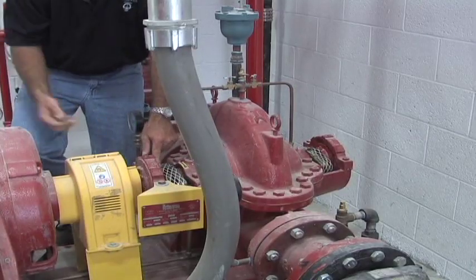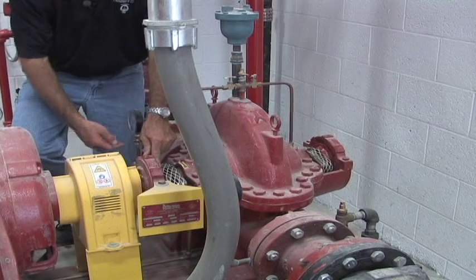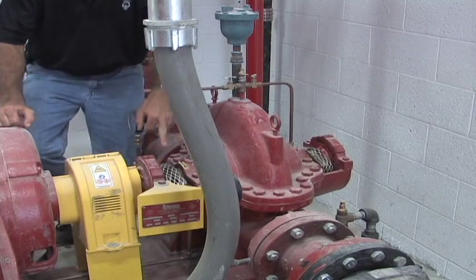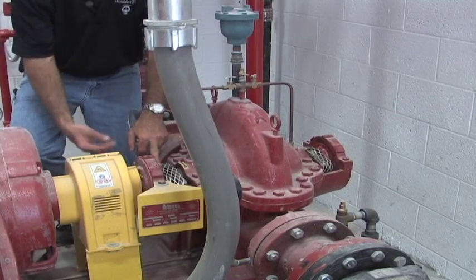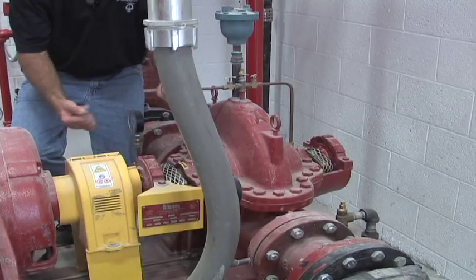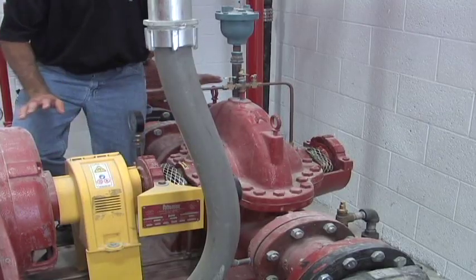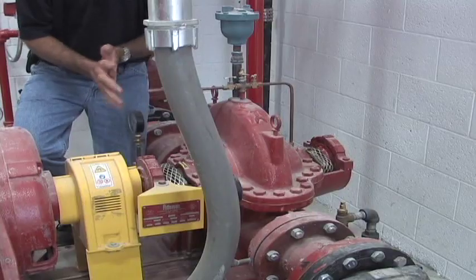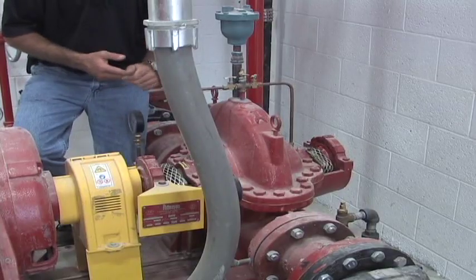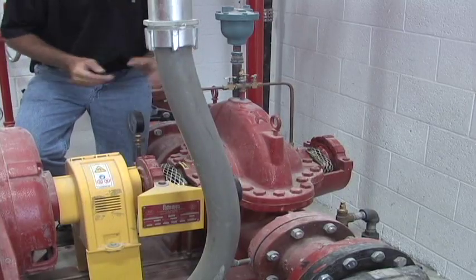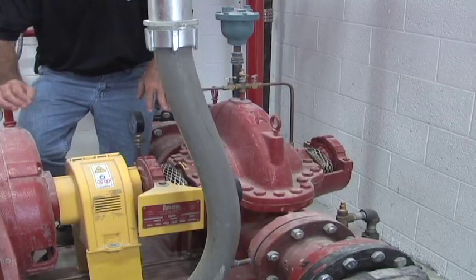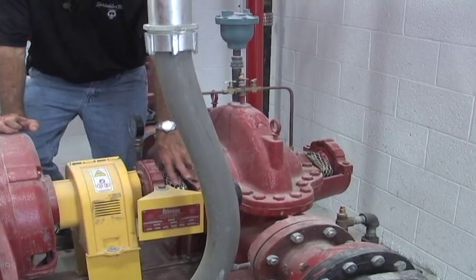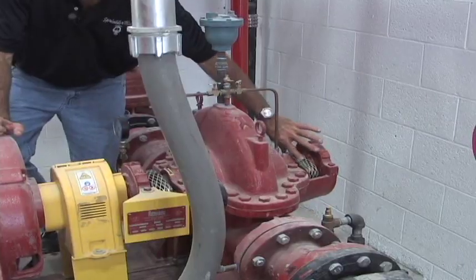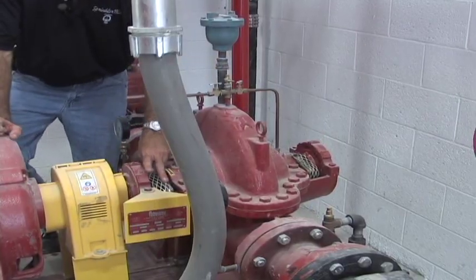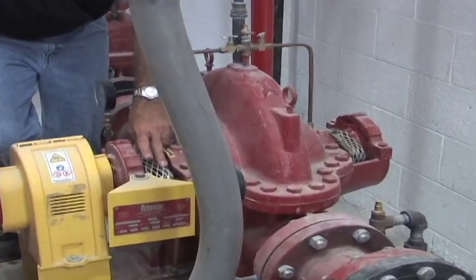You're going to grease here, you're going to pull the Allen wrench screw out of the bottom, you're going to pump new grease from the top until the old stuff comes out, screw back in the bottom, give it 1 or 2 pumps. It's about the only maintenance that you have that's going to go under the electric fire pump on your annual basis. Everything else is going to be pretty much preventative maintenance. We have our drip cups right here on the inboard and on the outboard packing. These packings are supposed to drip. You should have 1 drip per second.